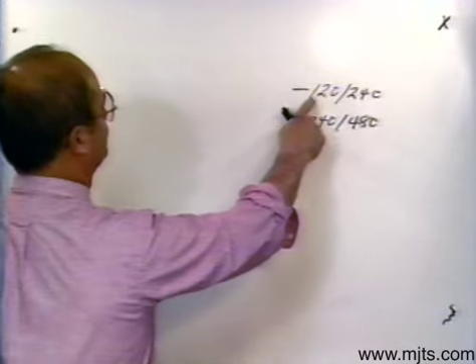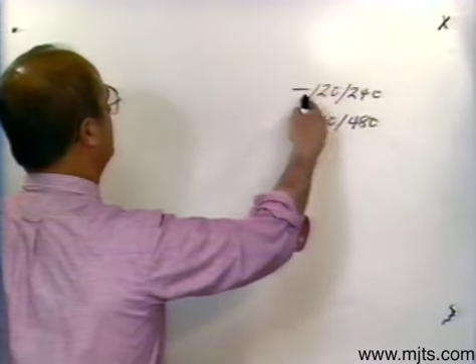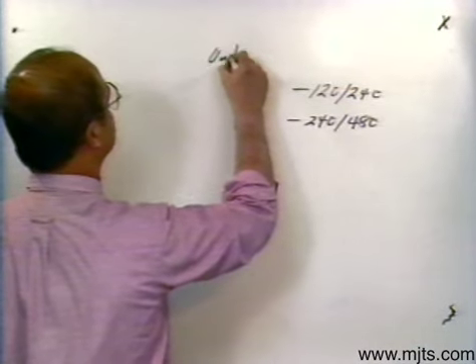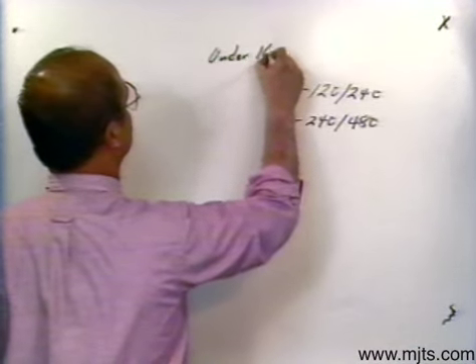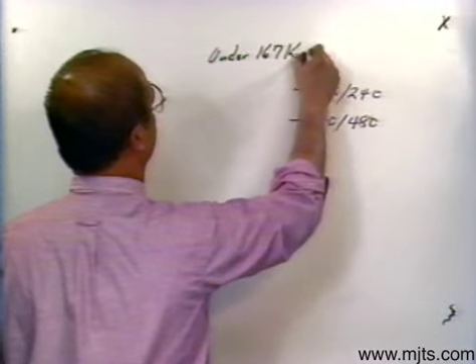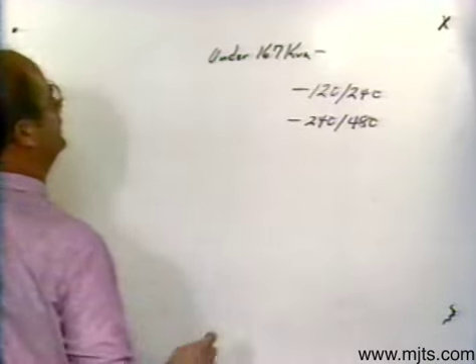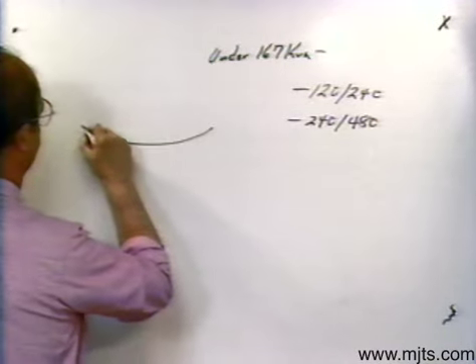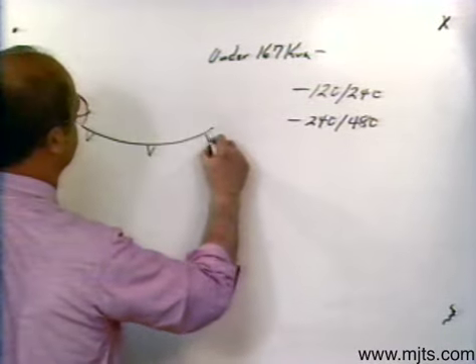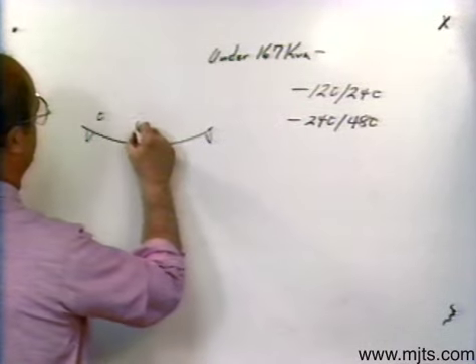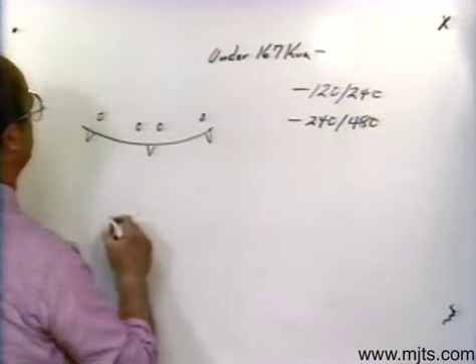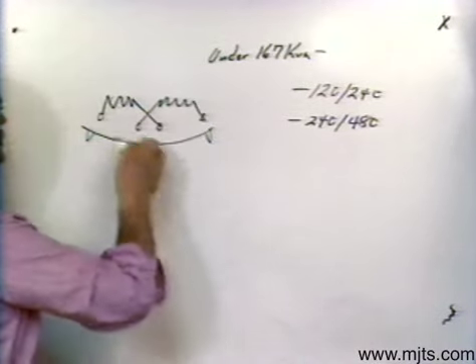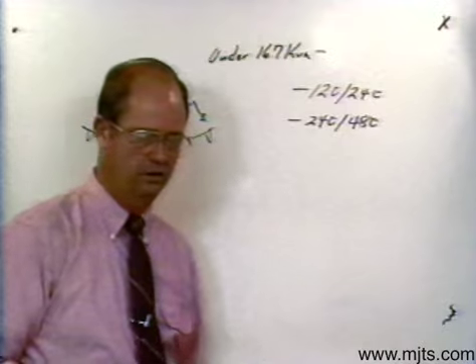If I have a transformer rated under 167 kVA, that transformer on the low side would have three bushings. It would have internal connections and the possibility of being either series or parallel connected.